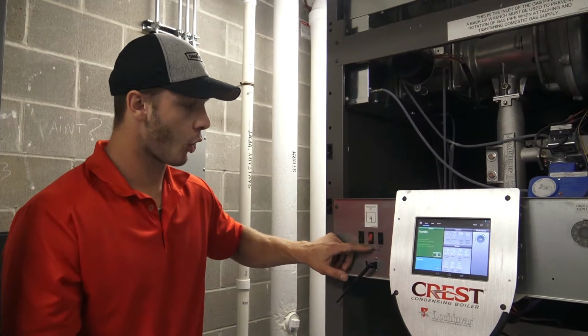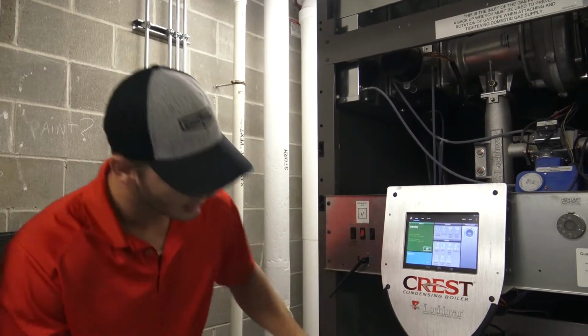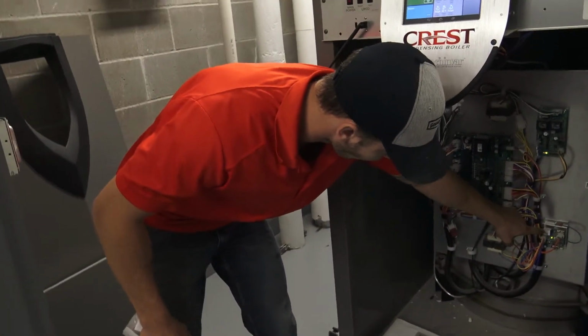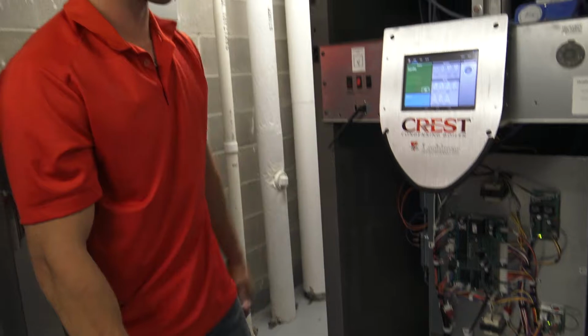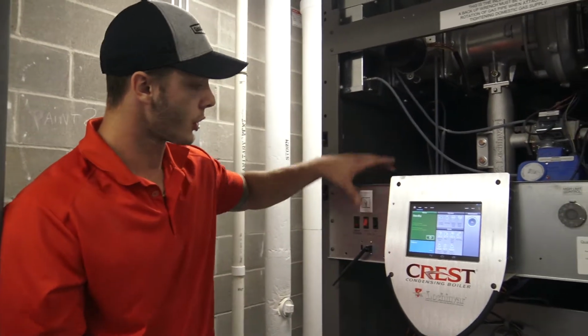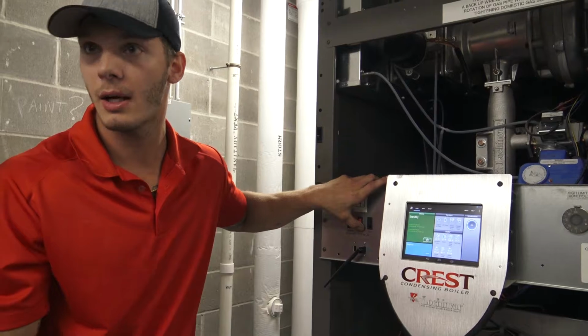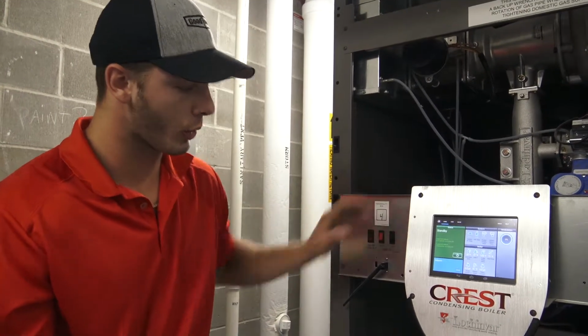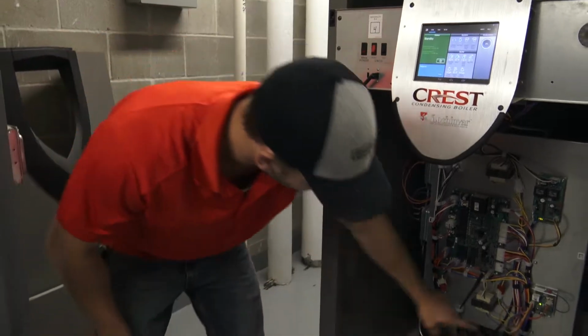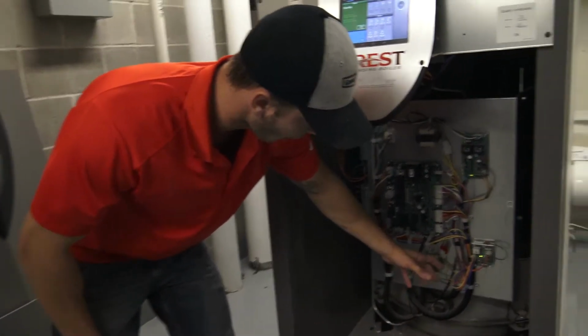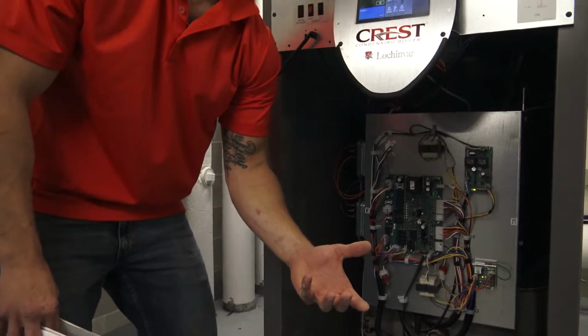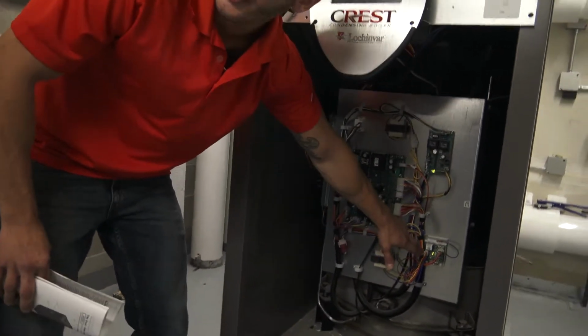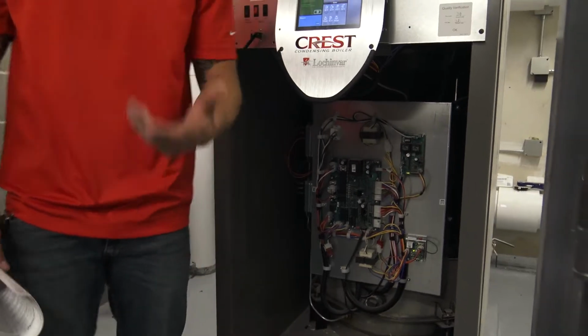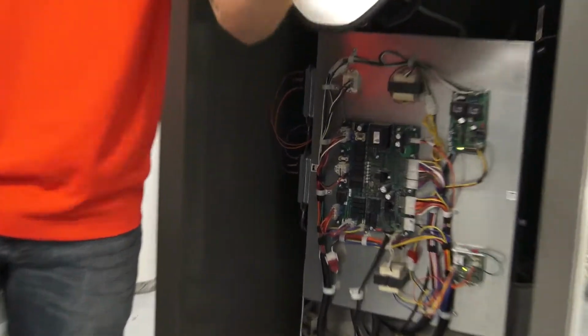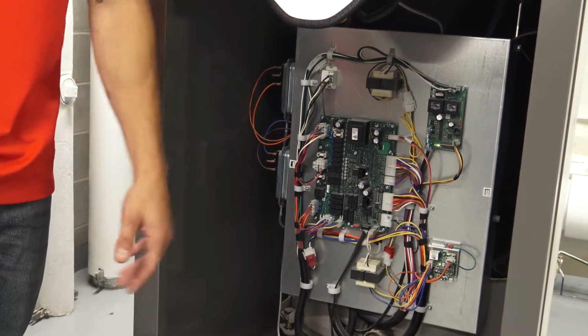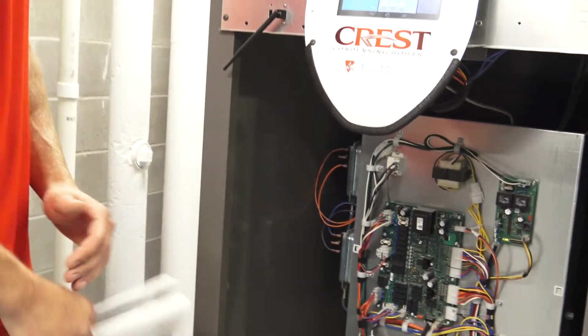Right here is going to be your low water cutoff reset, and that ties into right here. This is your low water cutoff card. So if you're ever having low water cutoff issues, what I recommend is you hit this reset button, you hold it for 5 seconds. If that doesn't work, you can pop this front panel off, which I did, and you'll be able to see if it is not working properly or if it does not have water there. You will see a red light on there. Then you'll know there's an issue. So if you don't reset it, I'll leave a business card and you would just call us, and we can figure something out. This is a Connexus board.